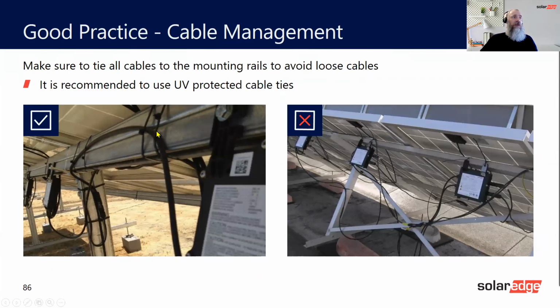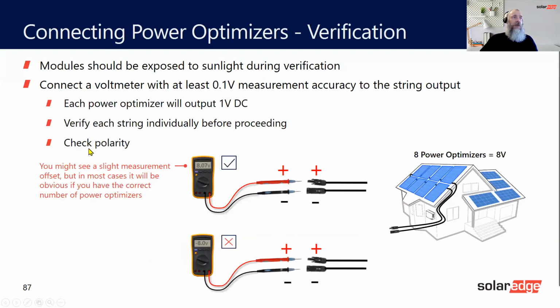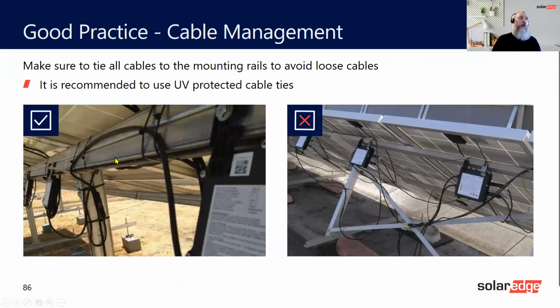These are secure. These have got cable ties on them. Cable ties are not the best in the world because they will deteriorate over time because they're only plastic. So they will basically become brittle and snap off. What you don't want is this cable rubbing. So these cables underneath here, they may be rubbing against the metal. They may be rubbing against the ballast here, the brick or the roof itself, or a tile. And also don't secure the optimizers. These are very old optimizers with cable ties.